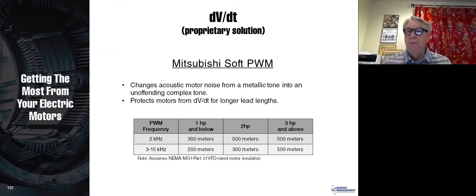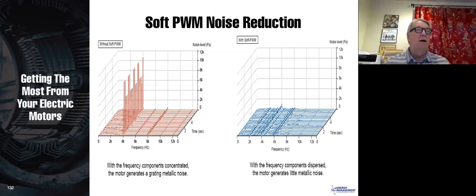There are some drives, Mitsubishi is not the only one, but sometimes it's hard to find this information, who have proprietary solutions. This is Mitsubishi's, they call it soft PWM. And if you have a VFD rated motor, NEMA MG1 Part 31 with high spike wire, you can go up to 500 meters for 3 horsepower and above without requiring a dV/dt filter. Instead of just having a standard frequency, they vary that frequency. You can see in the test here, this is a 4 kilohertz frequency. This is soft PWM, where they vary the frequency between 2 and 6 kilohertz, and that prevents most of those reflected waves and the resonances from occurring. Again, this is a patented way of doing things, but we've tested it, and it does a marvelous job.